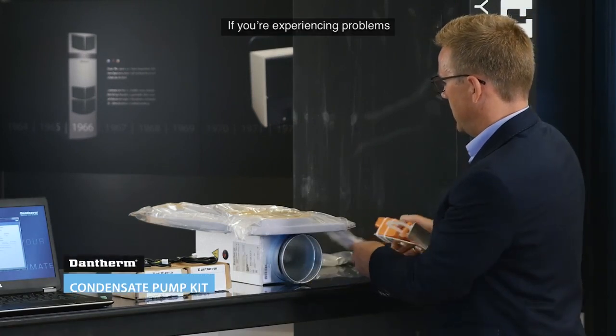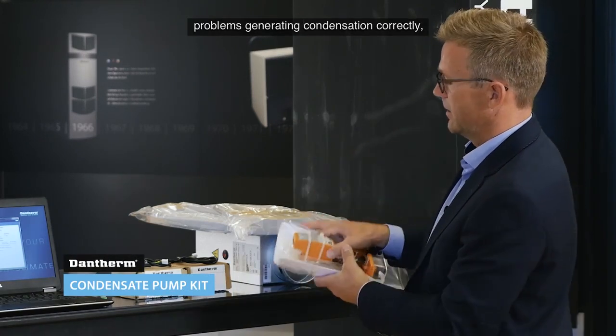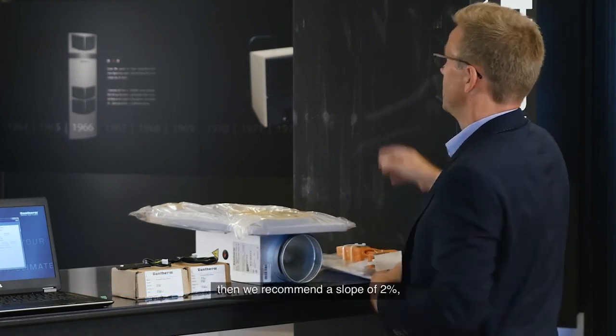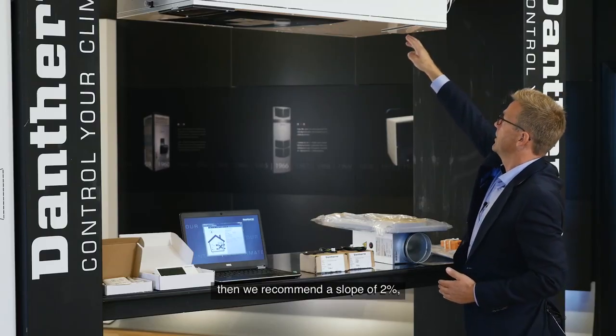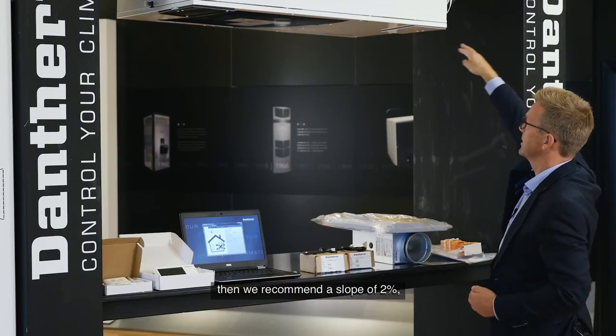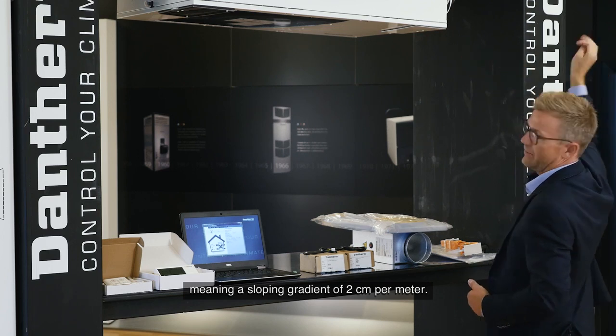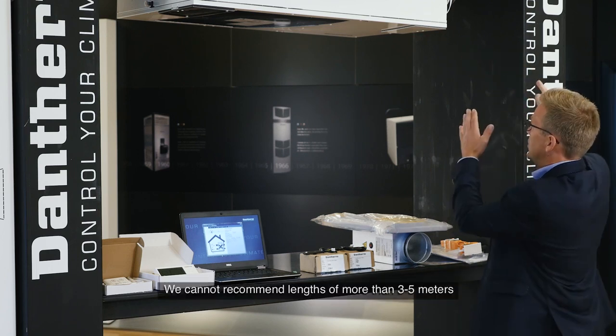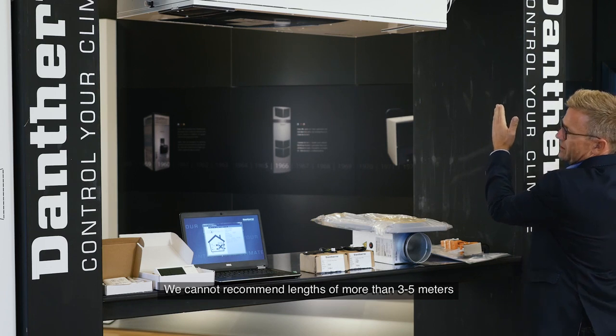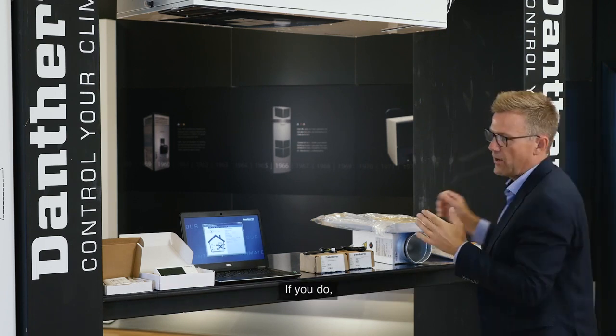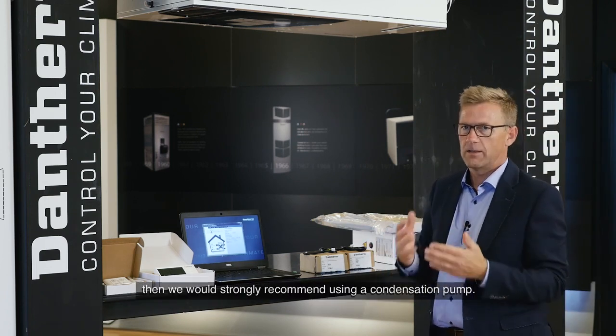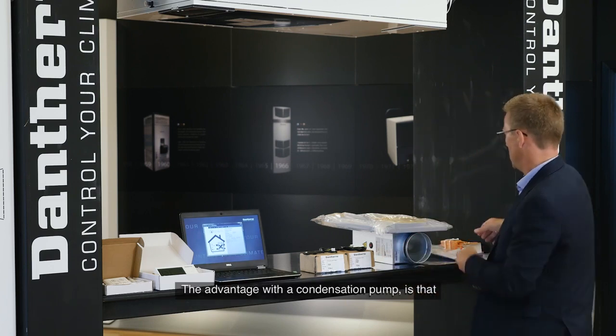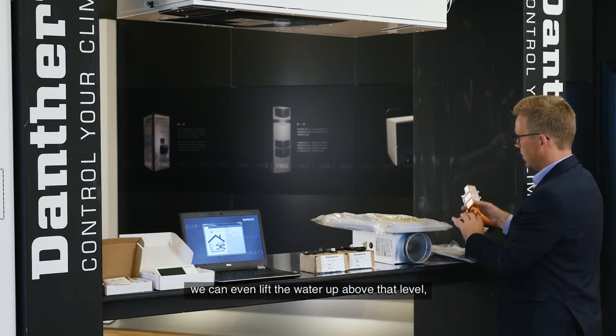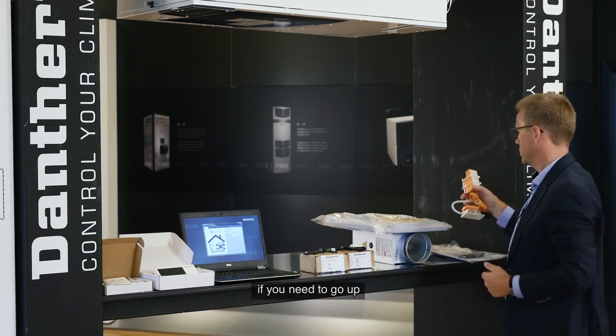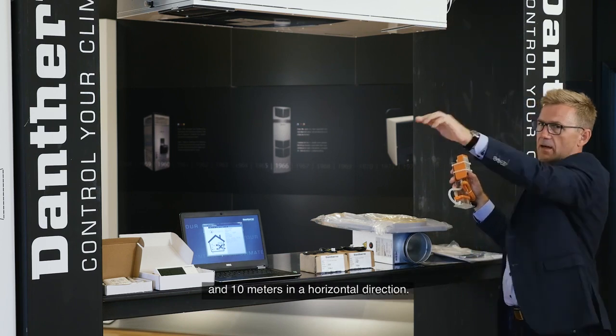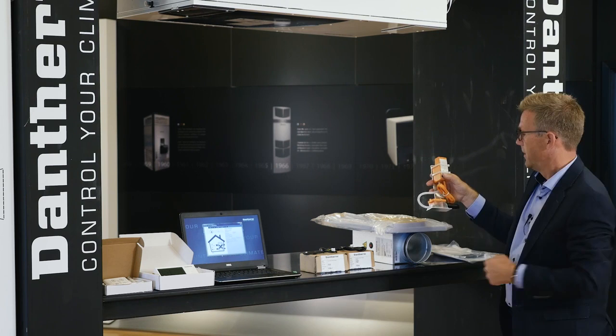If you have a challenge making the condensate drain correctly, because we prescribe that you need to have a slope of at least 2%, meaning 2 centimeters lower for every meter, and we don't advise having more than 3 to 5 meters distance to your sewage, then we recommend a condensate pump. With a condensate pump, we can even lift the condensate water above that level if you need to go up, and we can at least go 10 meters in a horizontal direction.